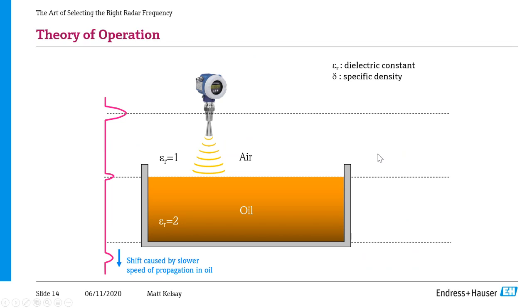That peak is actually the tank bottom, but you see it's shifted below where the actual bottom of the tank is. And that's due to the fact that that radar signal is traveling actually slower through the oil than it is through the air, so you get what we see in that shift. That's part of why measuring in a lower dielectric media is a little more difficult than a high dielectric. You often see multiple peaks. Things are sometimes shifted from where they actually are in the tank. So it's just a little more signal processing that the radar has to do.